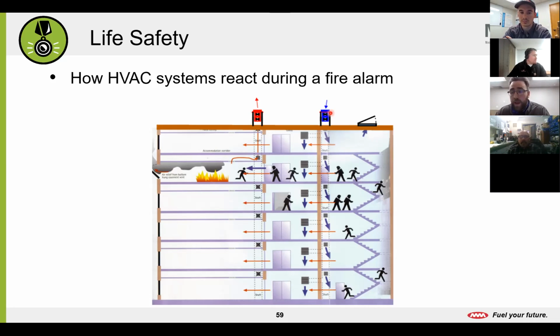This is equipment that, when we have maintenance, is included in our maintenance. It's imperative that it gets done, but it is tied to our fire panel, so there is a little bit of coordination involved. We do have to get whoever your fire and life safety vendor is on site to coordinate so we can cycle these systems. These systems are directly tied to our fire system, and if we try to override them and kick them on, it causes more of a headache and many more problems than we want to delve into.